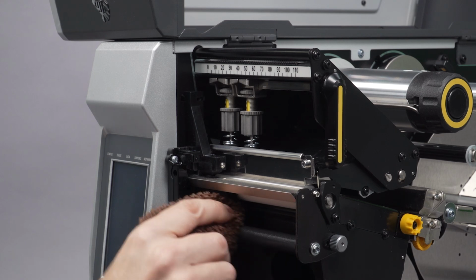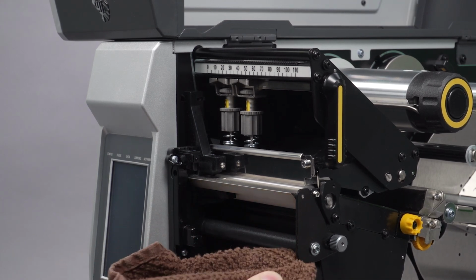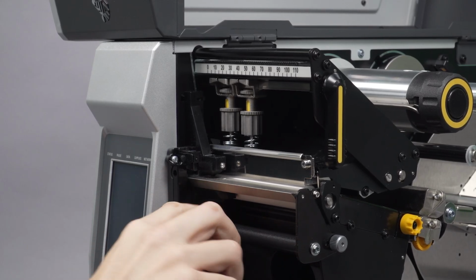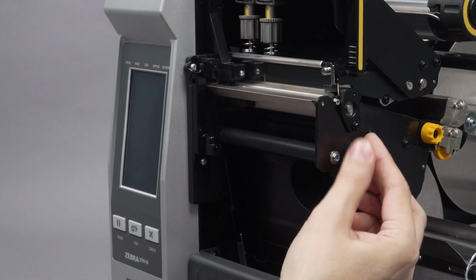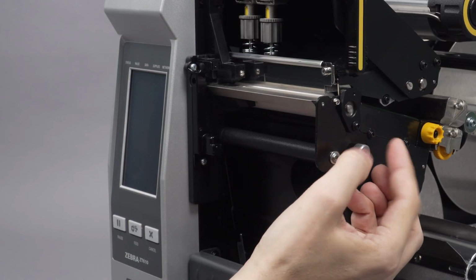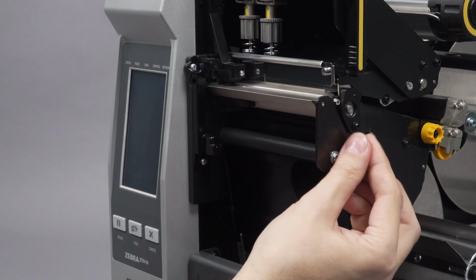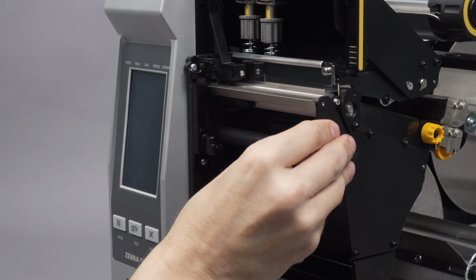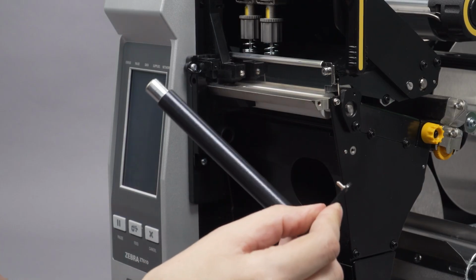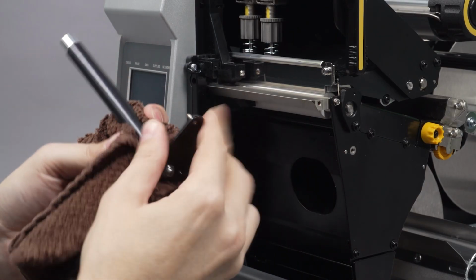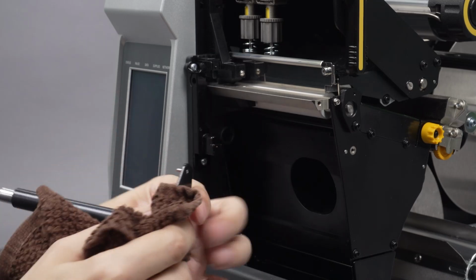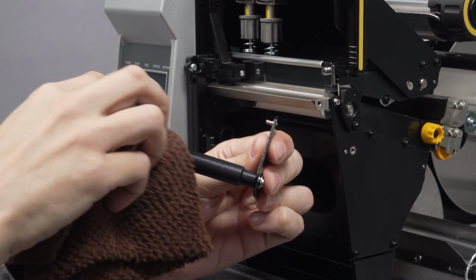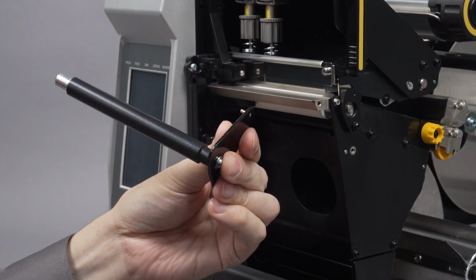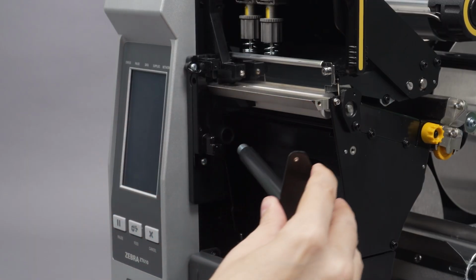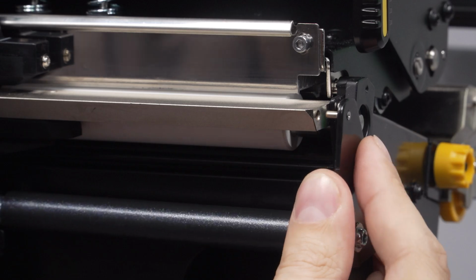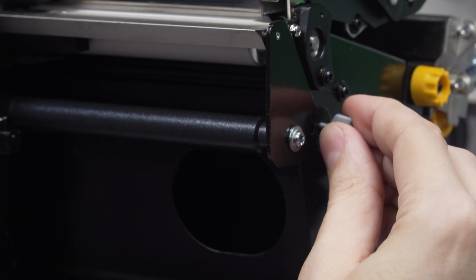Wipe the exposed surface of the peel rod. If adhesive or labels are stuck on or behind it, you may need to remove it to clean it. To remove the peel rod, remove the hand tightening screw. The whole assembly slides out. Clean all surfaces of the peel rod with the swab or cloth. When reinstalling the peel rod, line up the guide pin at the top of the tear bar plate and push the rod into place. Then reinstall the hand tightening screw.